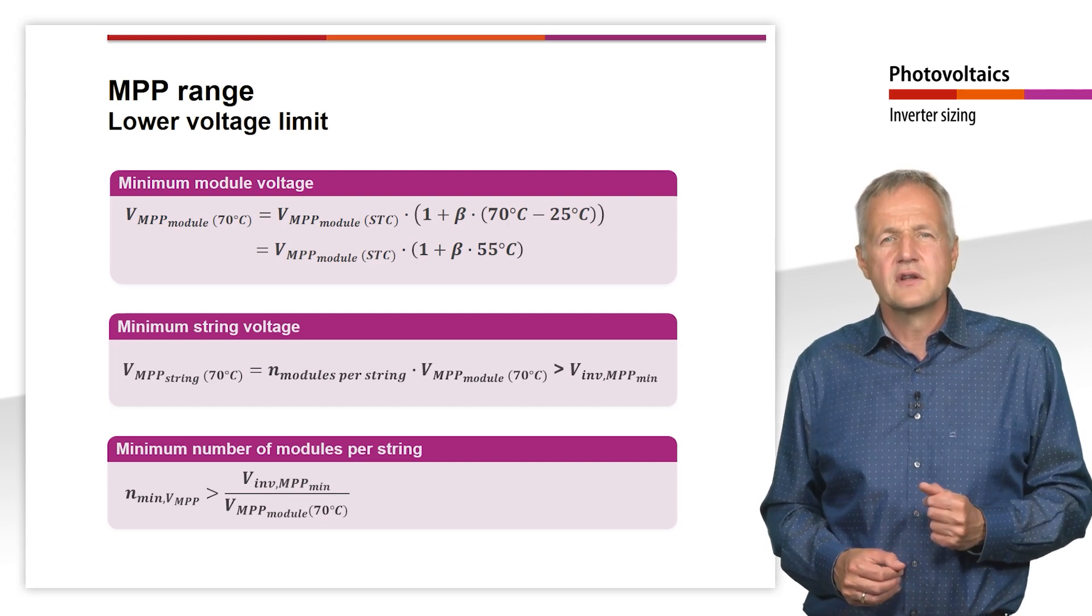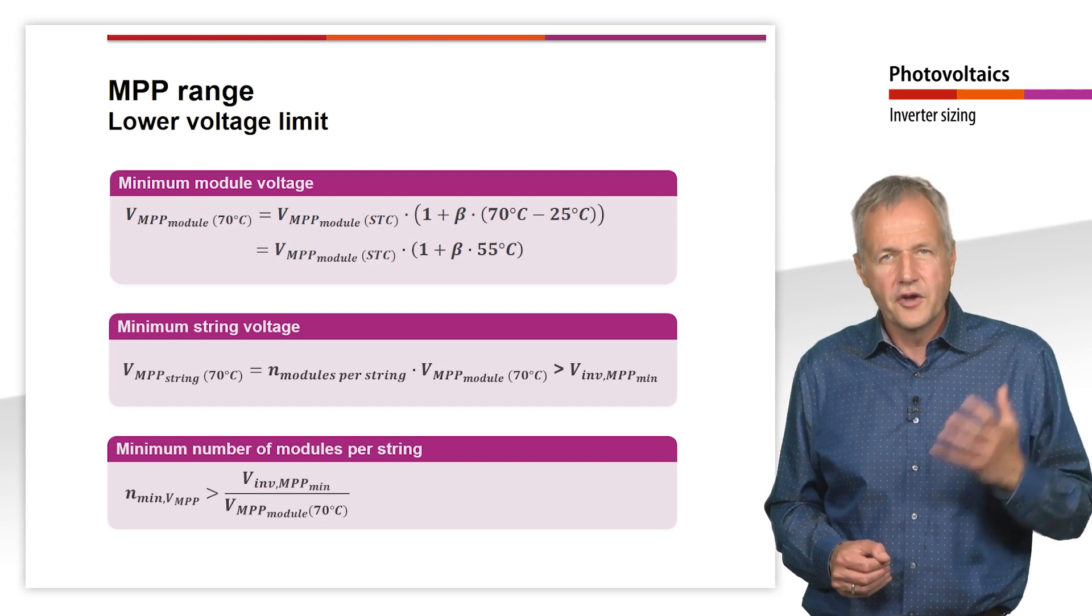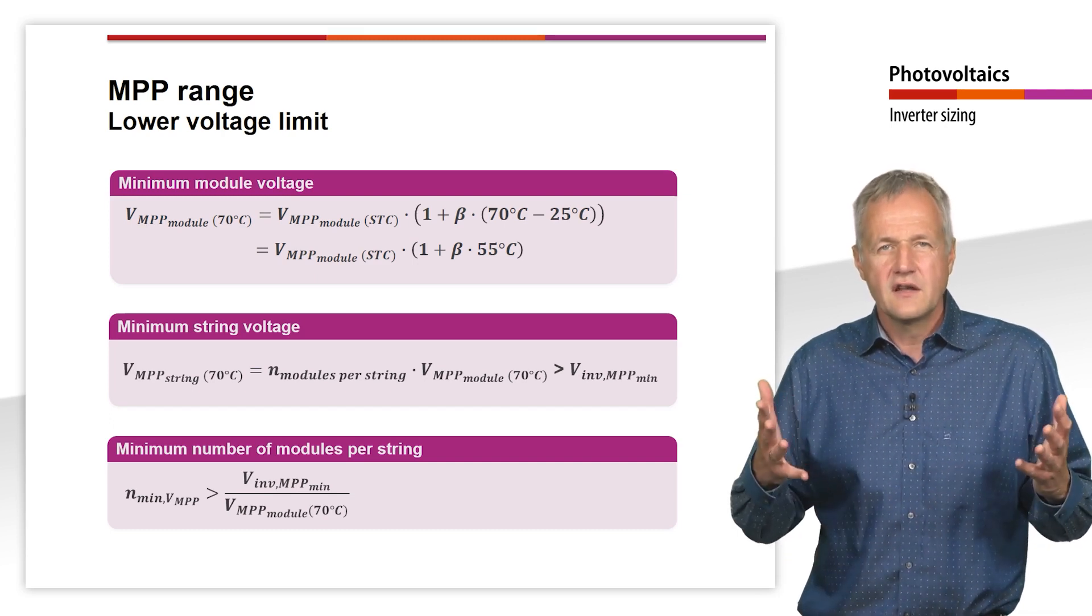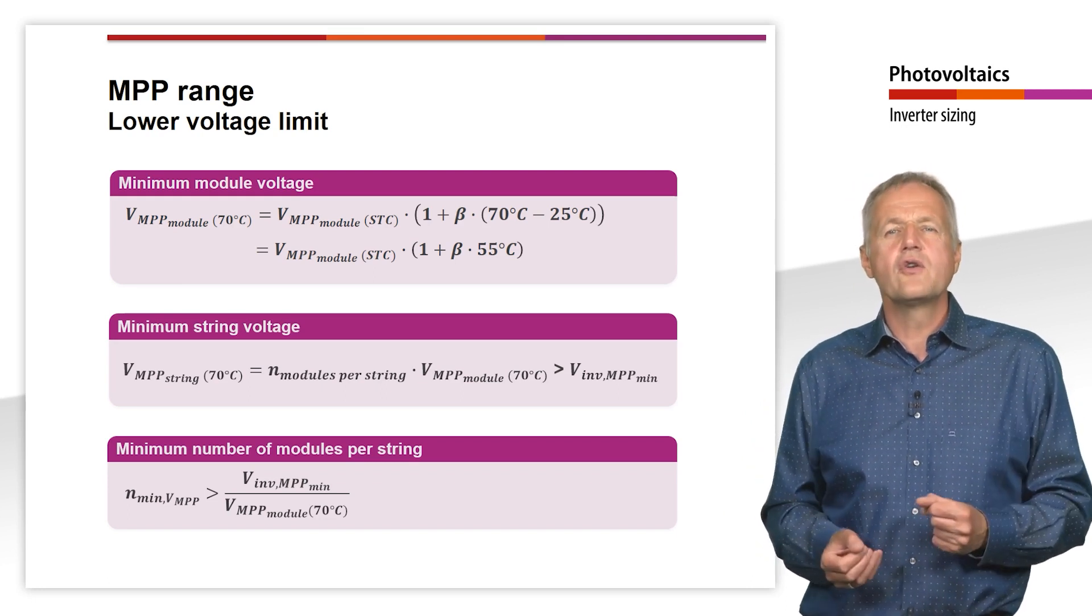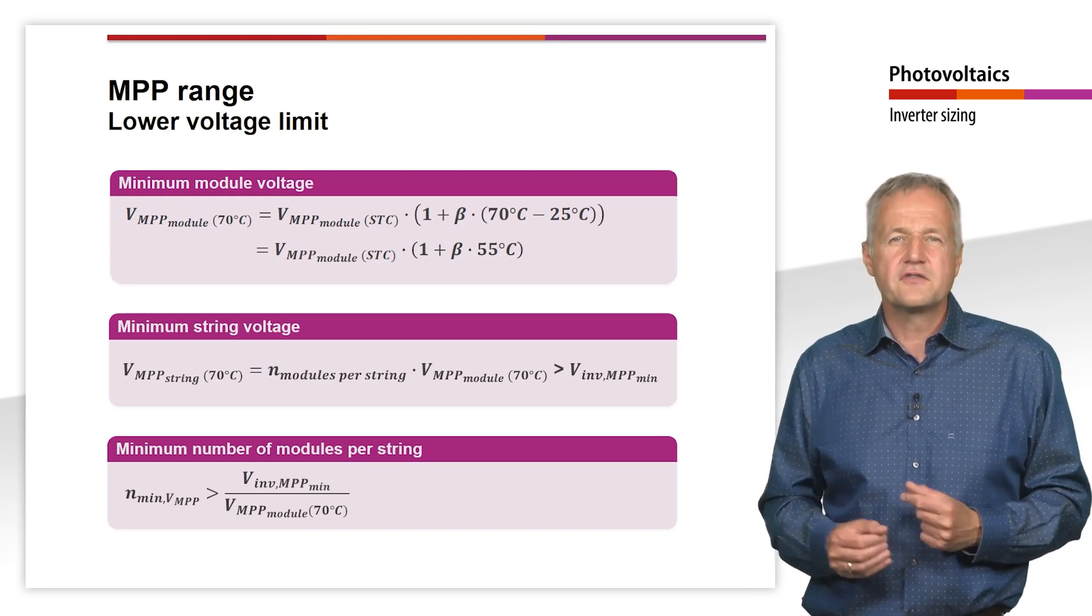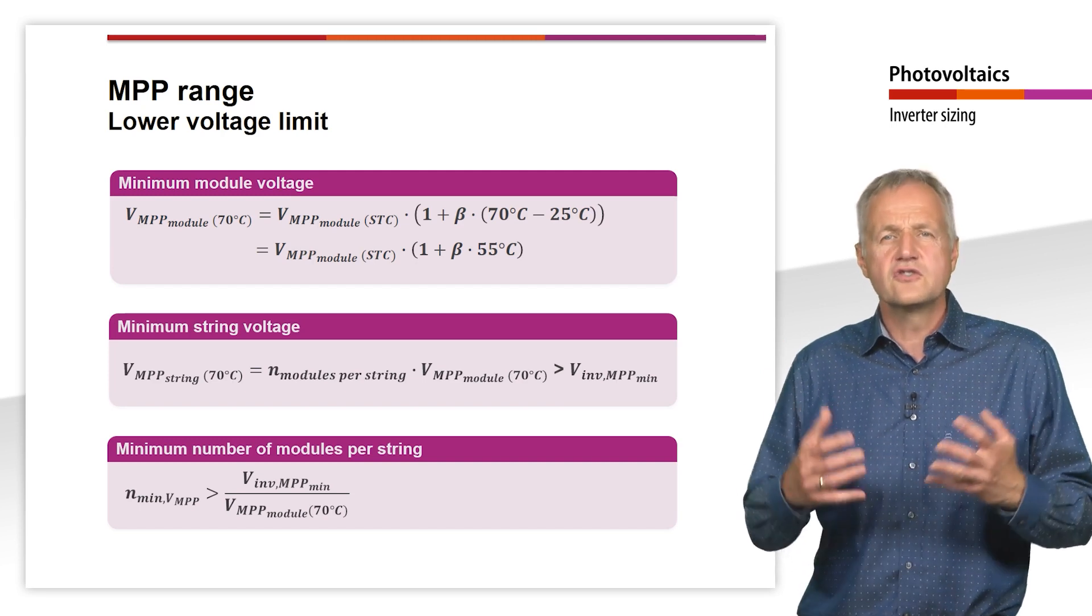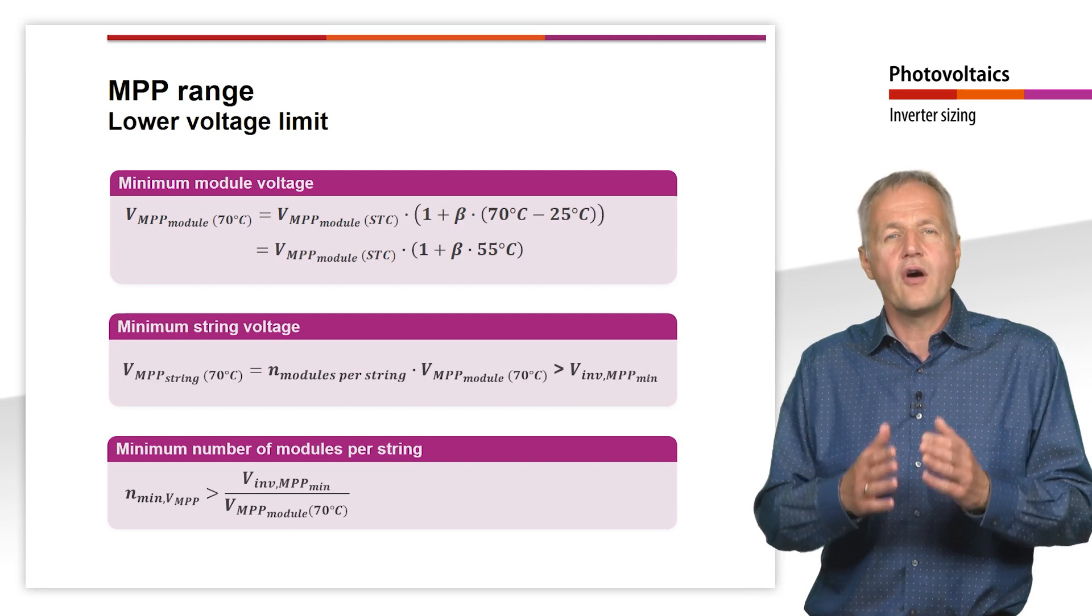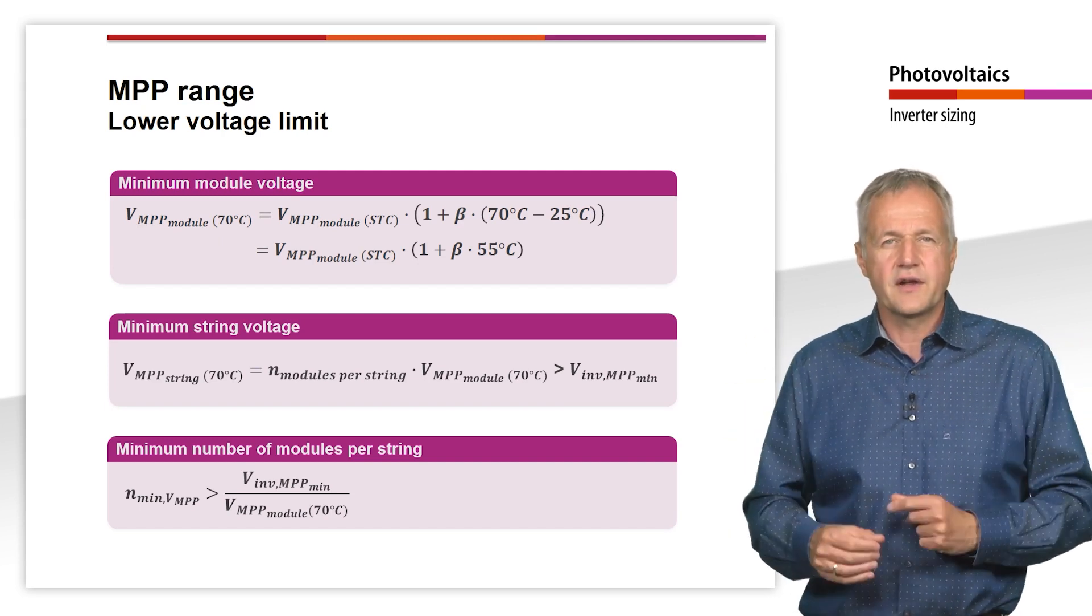If you connect too few modules in series, the inverter will not be damaged. However, you have to expect that especially in the warmer summer months, the inverter can no longer operate the solar modules at the MPP and you have to accept higher yield losses. In practice, this should of course be avoided and a sufficient number of solar modules should always be connected together in one string.